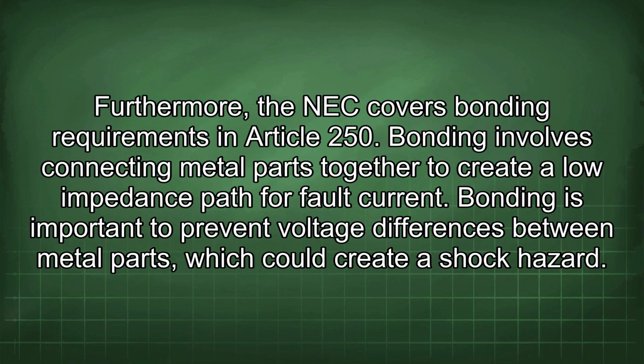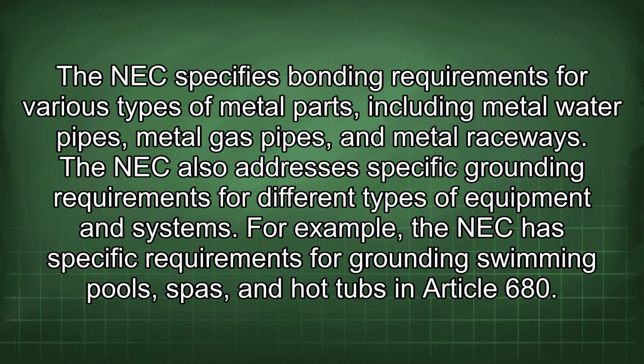Furthermore, the NEC covers bonding requirements in Article 250. Bonding involves connecting metal parts together to create a low impedance path for fault current. Bonding is important to prevent voltage differences between metal parts, which could create a shock hazard. The NEC specifies bonding requirements for various types of metal parts, including metal water pipes, metal gas pipes, and metal raceways.